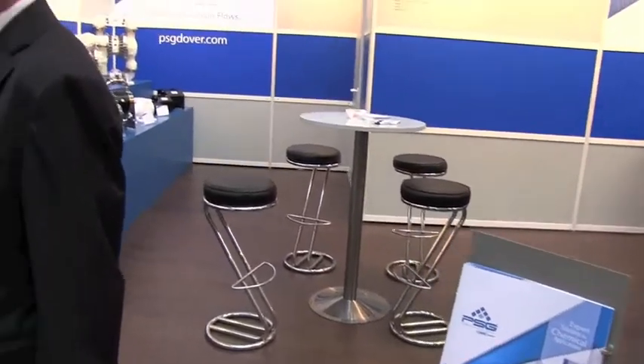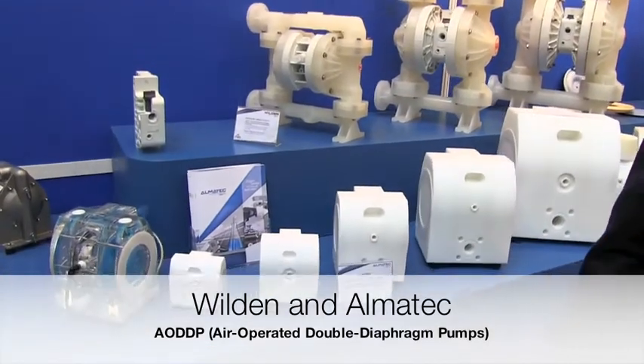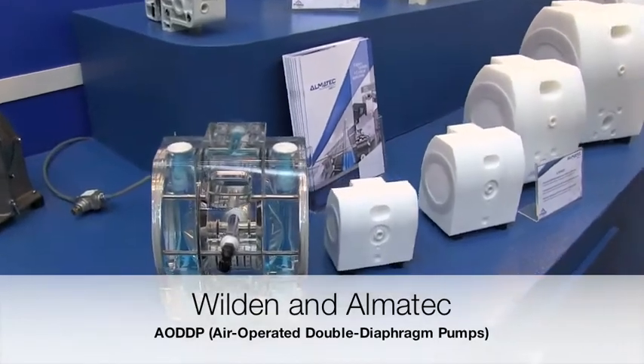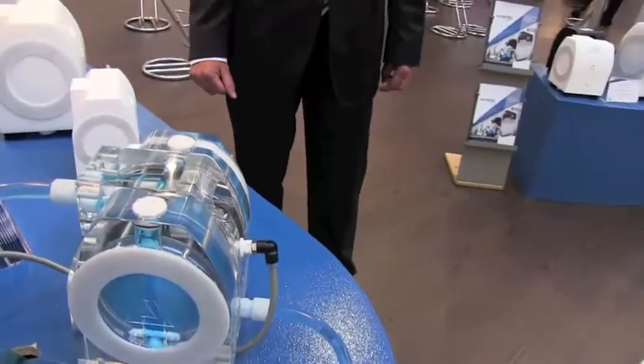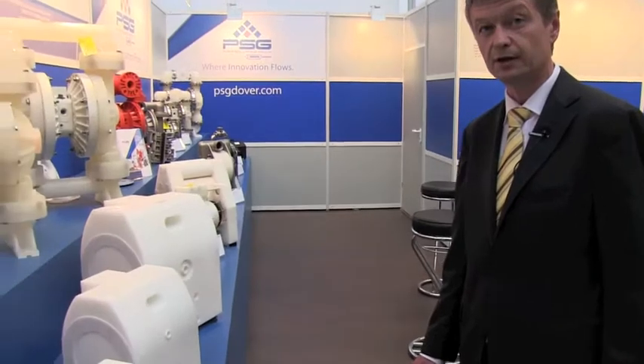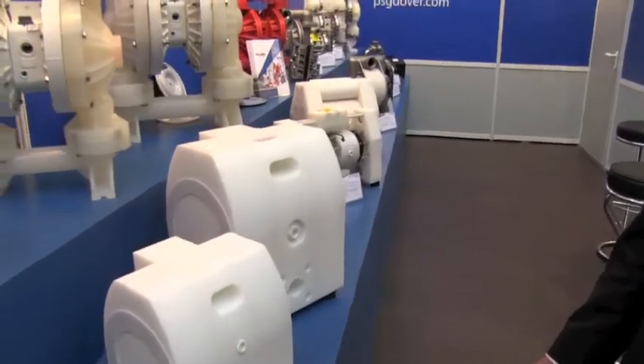We have here on this side the air-operated double diaphragm pumps from Almatec and Wilden. The pumps have several advantages and are very often used in the chemical industry. They have no rotating seals, they can run dry, they are self-priming, and they can be handled very easily. We have the Almatec pumps made of plastic materials — polyethylene and PTFE. Over there we have the Wilden pumps made of polypropylene and PVDF.